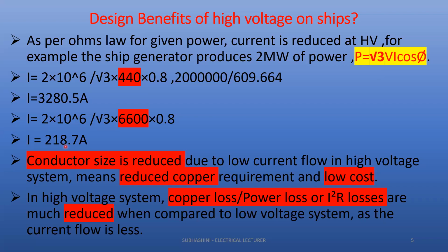So the next advantage is, since we take copper loss, or we say it as power loss, power loss is equal to I square R loss. So here I have shown the formula, I square R loss. Current is reduced from 3300 to 220, so the square of the current will also get reduced. I square R means the square of the current. So the current is getting reduced, and the loss will obviously get reduced. Simple calculation. So when compared to a low voltage system, the current flow is less.